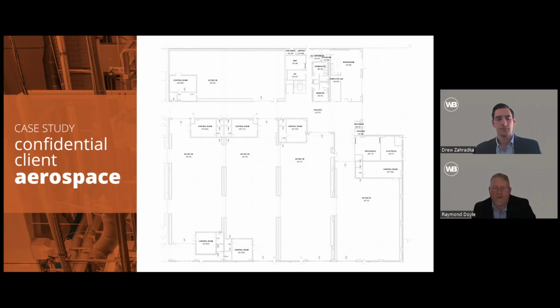And what we did in that environment was originally we talked about things like raised floor, unidirectional top to bottom. And it came down to the assembly was going to be on platforms up above the floor, and with some testing and some verification, we were able to understand that they could use low wall returns and not have to go all the way to the raised floor solution and design a raised floor to a very high load capacity. So that was a success story in the world of aerospace and saved them a lot of money.